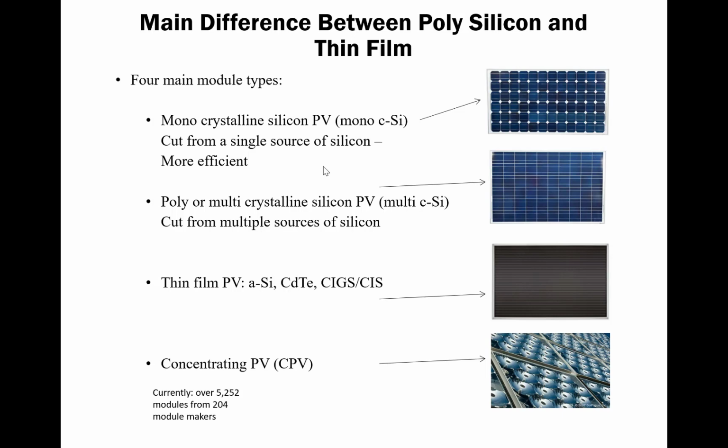When I talk about efficiency in solar power, you've got to be really careful. Efficiency doesn't really affect the cost. You measure cost in terms of cost per kilowatt output. The thing that efficiency measures is how many modules you have to put there to get that kilowatt, and that affects the area. And if you have very cheap land, you don't care at all about efficiency. If you're limited to a rooftop and want a whole bunch of power from your rooftop, you care very much about the efficiency.